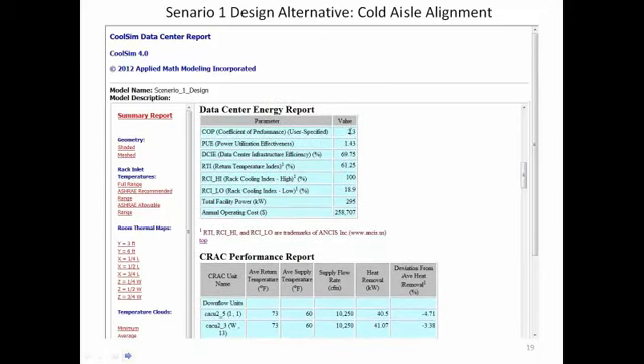That's correct. And on this model, everybody can notice we took out all the underfloor obstructions as well. Yeah. So you've got better air distribution coming out of the floor. If we looked at the CRAC report, we'd see more even distribution of load on the CRAC units as well. Let's take a look at the airflow coming from the tiles here and see what we've got for short circuiting. A lot less than we had, so it's much better now. We still have short circuiting going on, bypass, but we're going to have a little because we've got too much air. So that's just going to be the case, but it's certainly not as bad as it was before. And it's not shorting out so badly like it was over in this region. So in general, things are a lot better than they were.